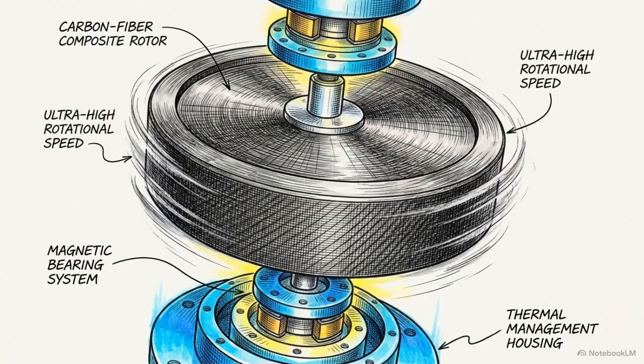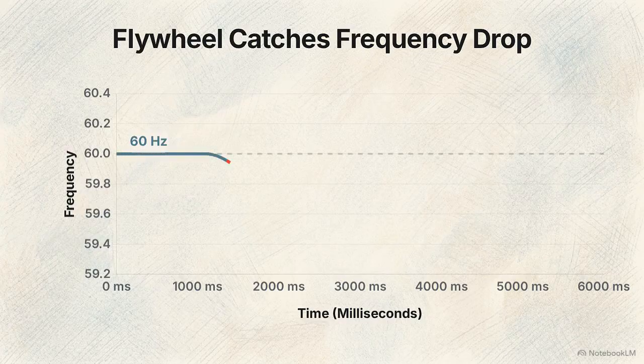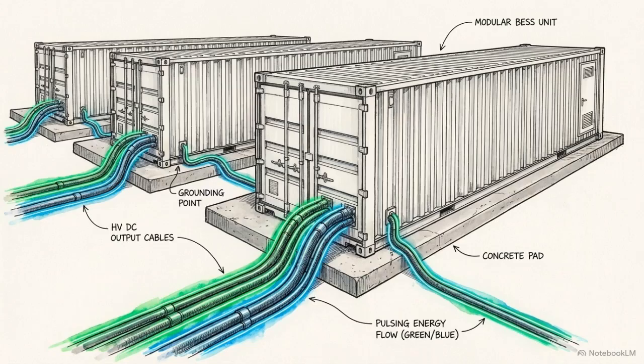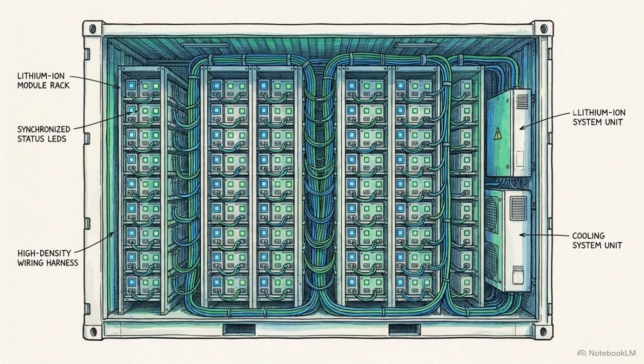We can observe how these technological modalities operate together by deconstructing their orchestrated sequential response to a sudden catastrophic drop in renewable grid generation. In the very first millisecond of the event, mechanical flywheels instantly dump their kinetic energy to catch the immediate frequency collapse, stabilizing the line before automated breakers can trip. Over the next several seconds, the BESS power conversion system takes over. It injects sustained synthetic inertia, successfully bridging the gap while thermal plants attempt to ramp up.